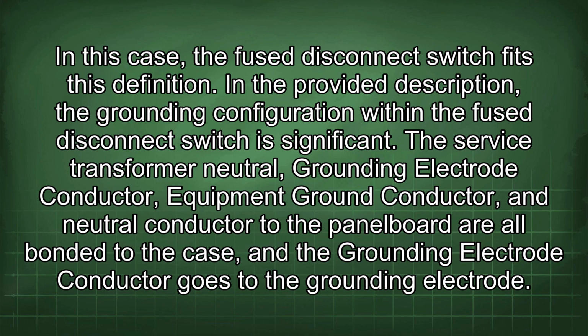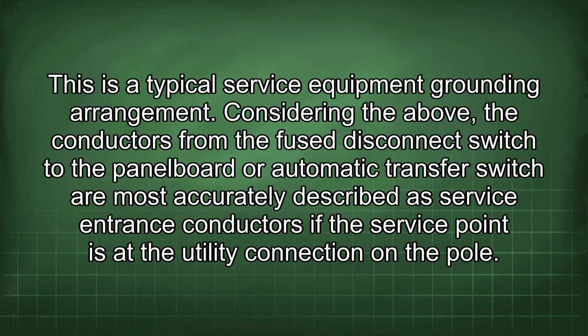In the provided description, the grounding configuration within the fuse disconnect switch is significant. The service transformer neutral, grounding electrode conductor, equipment ground conductor, and neutral conductor to the panel board are all bonded to the case, and the grounding electrode conductor goes to the grounding electrode. This is a typical service equipment grounding arrangement.